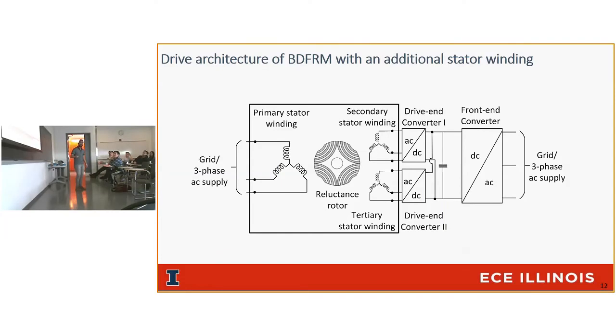So you have a primary stator, again directly connected to your 3-phase AC source. You have 2 windings which are controllable. One is the secondary stator, another is the tertiary stator winding. Both have to be controlled. So there are 2 inverters over here, drive-end converter 1 and drive-end converter 2. By the introduction of this tertiary stator winding, we are expecting to increase some amount of torque at the expense of including some additional power electronics. So again, there is a trade-off over here between getting extra power and including some amount of extra power electronics as well. So how much torque do we expect out of this by the addition of this winding?